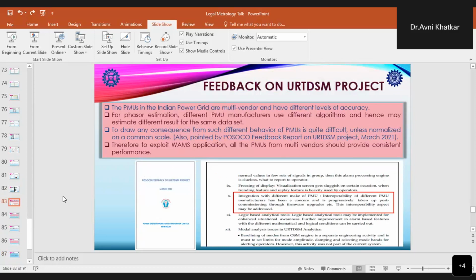And based on the feedback, now the first phase of the URTDSM 1 project is over, and now the country is moving towards the implementation of phase 2. Before that, a feedback on the URTDSM was published in March 21 by POSOCO. One main problem which was seen was that the PMUs in the Indian power grid, as we all know, are multi-vendor. They are from different manufacturers and have different levels of accuracy. For phasor estimation, the PMUs from different manufacturers use different algorithms, so the phasor estimation methods are different. So we are getting different results. It is very difficult to draw any conclusions from these different behaviors of the PMUs unless they are normalized on a common scale. This was also pointed out by the POSOCO feedback report.